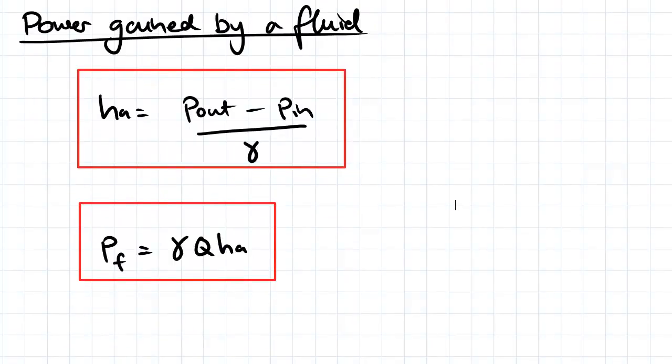In terms of the power gained by our fluid, that's measured as a gain in head, HA. That's approximately equal to—assuming no change in height throughout our pump—the pressure that we get out of our pump minus the pressure that goes in.